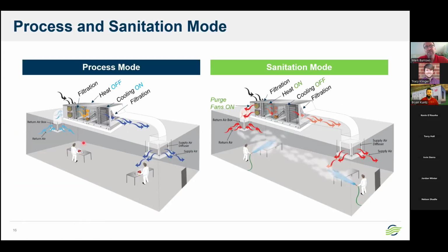Sanitation mode, that's exactly the same unit. We're just going to flip this from process to 100% makeup air. Cooling coil is typically locked out in sanitation. We're going to take the raw ambient air. If it's summertime, we're going to flush that into the room and then take all this moisture out to atmosphere. If it's cold outside, typically we'll supply a direct fire burner. It's going to heat up to maybe 80, 85 degree discharge. That warm air is then put in the room. You can imagine how much moisture is absorbed in that sponge-like environment. Again, wicking the air off the ceiling and taking it right out to atmosphere. And we can also offer indirect fired burners as well, just to note that.